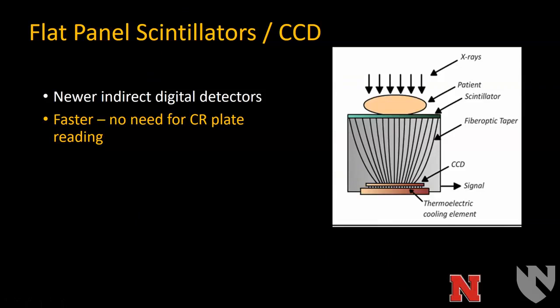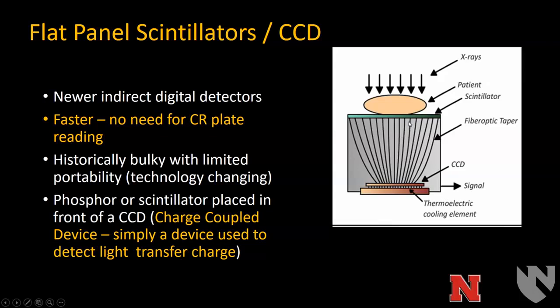Flat panel scintillators using CCDs are types of indirect digital detectors. They have a scintillator, but CCDs can only be made so large, so a fiber optic taper is used to reduce the image size to fit the detector. The advantage here, compared to computed radiography, is that you don't have to physically read off a storage phosphor — you get the image immediately. Historically, the problem with these systems was that they were more bulky, though that's changing.